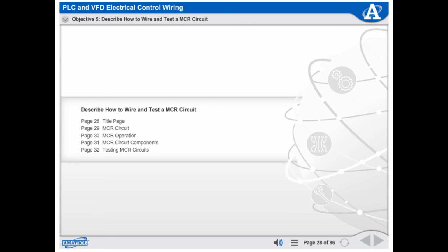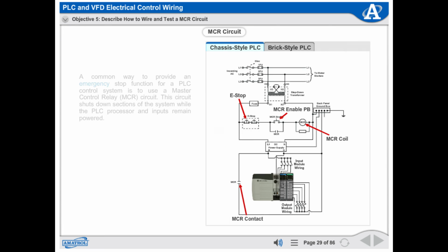Describe how to wire and test a master control relay circuit. A common way to provide an emergency stop function for a PLC control system is to use a master control relay circuit. This circuit shuts down sections of the system while the PLC processor and inputs remain powered.